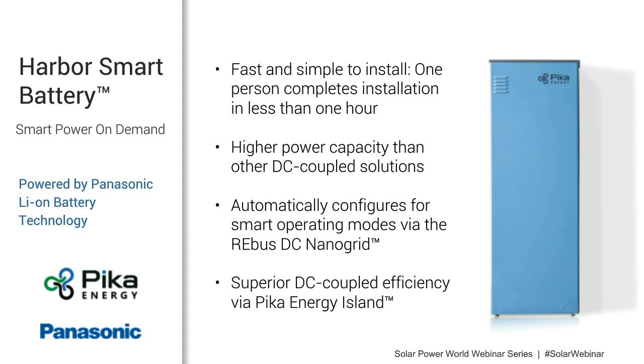With this design, the battery is coupled directly on the DC side of the Pika Energy Island system, which not only allows higher efficiency but higher power capacity than other systems available on the market. With no auto transformer on our inverter, you can use the full inverter capacity for islanded loads, and the battery itself provides 6.7 continuous kilowatts of power. So really the difference there is that if you're islanding and using this battery for backup power, you're going to have a lot more available power, which makes it a pretty exciting product for anyone who's using it for backup power.